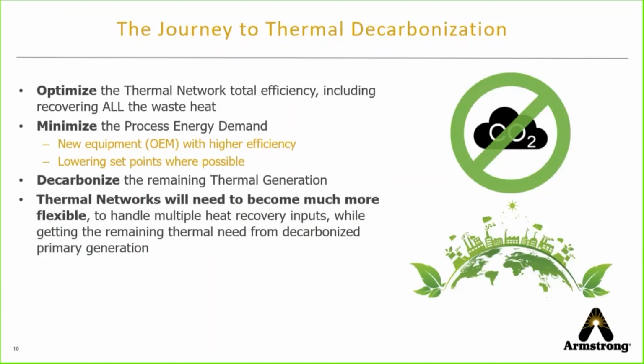And then take a look at lowering set points where practical. Do we generate hot water at 180 degrees only to use it for 30 minutes in the morning? The rest of the day we use 140 degrees? Why don't we take a look at generating at 140, reduce the primary heat demand that's needed, and then look at heat recovery to boost those temperatures up to those process needs when and where they need them.